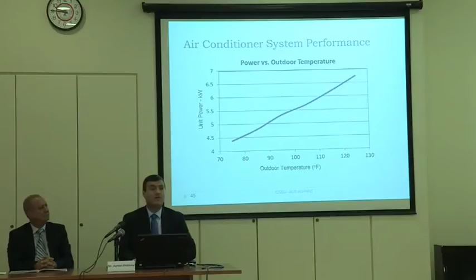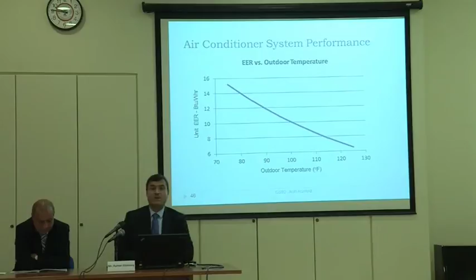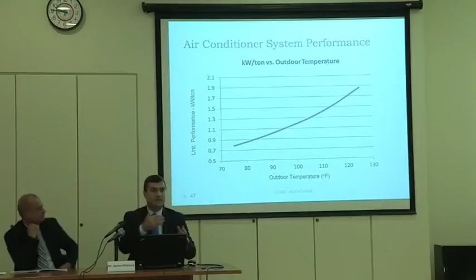This is very important. This is really the essence of the whole presentations and talks that Ayman has mentioned, that when we go to a higher ambient temperature, we're speaking about a different EER value range. The kilowatt per ton goes up by the same conversion factor because it is really the watt divided by the ton. Now, this is from our lab.